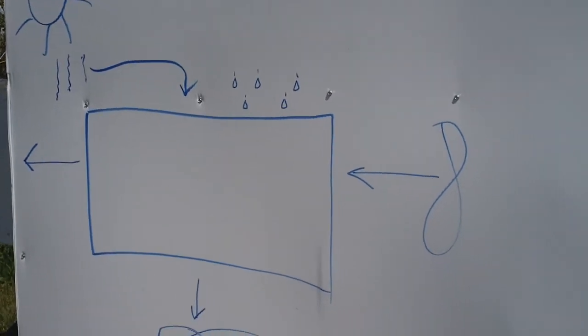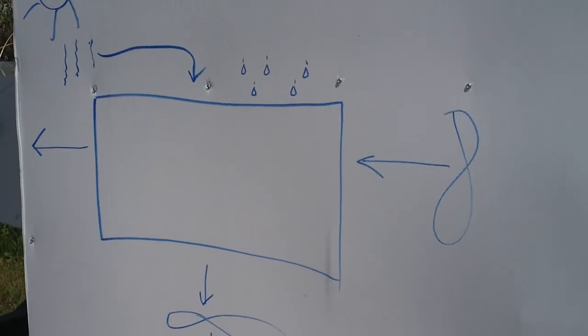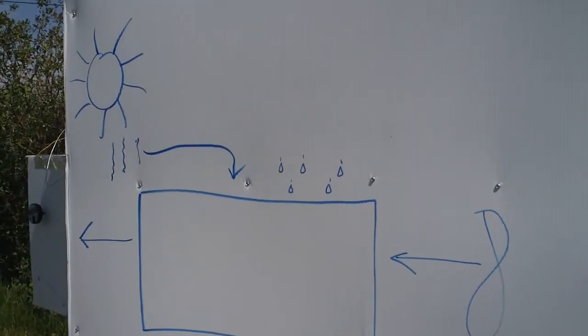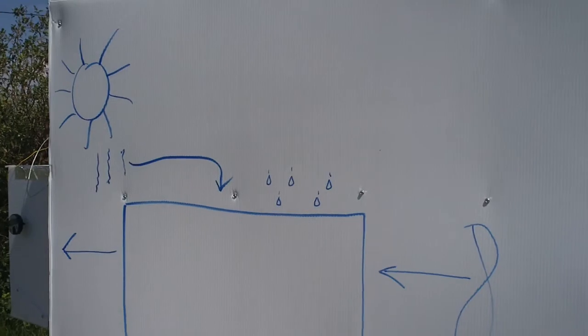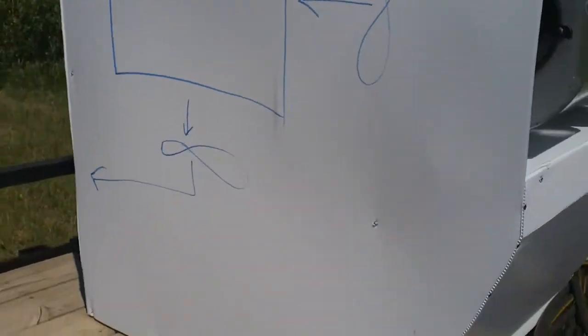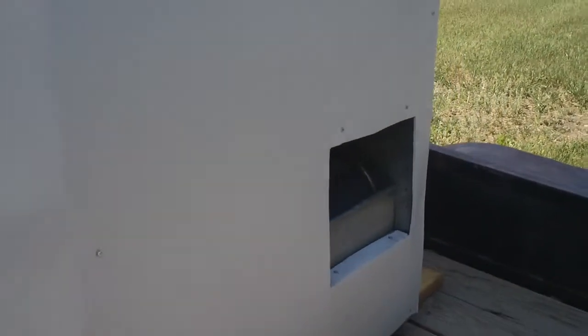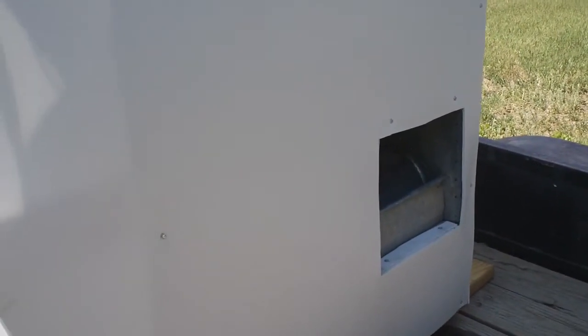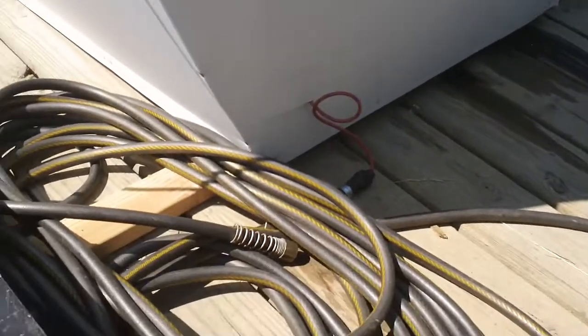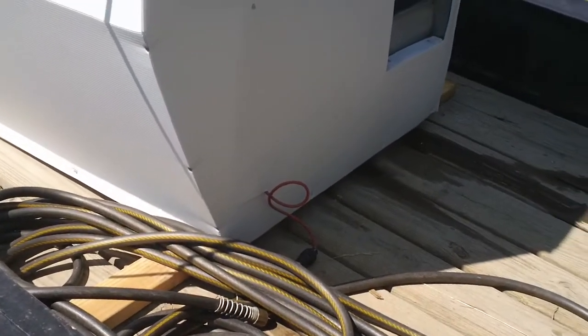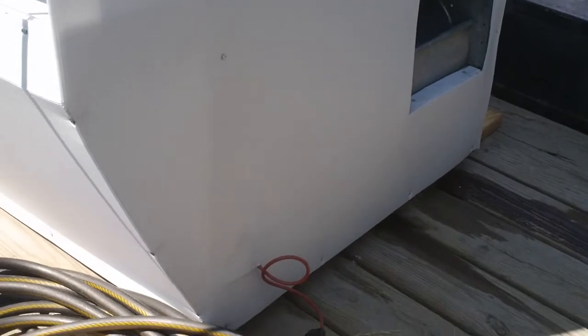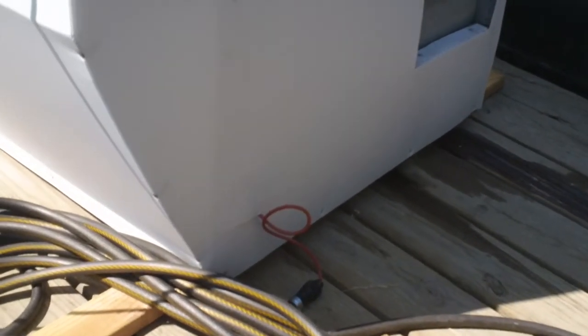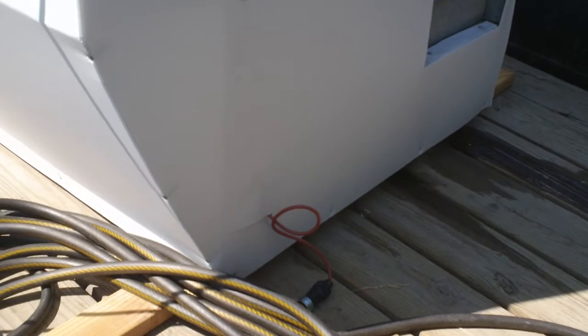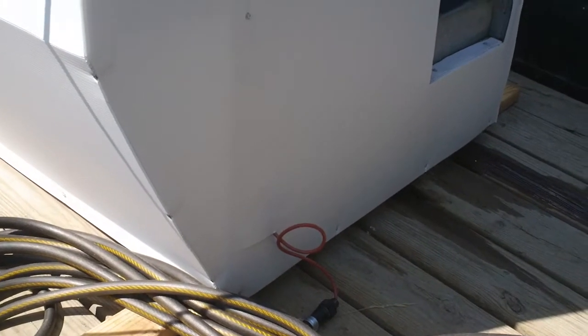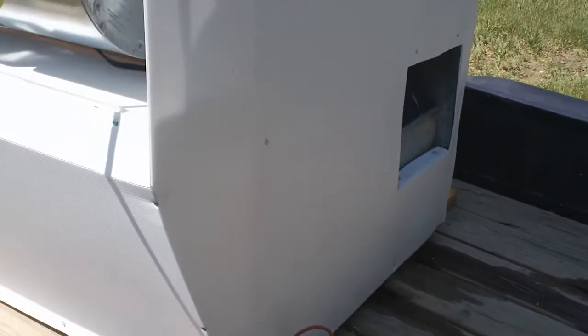This is an indirect evaporative process. Water's being dosed into the top, as well as we're pulling ambient air through using about a 4-ton or 1400 CFM squirrel cage blower, which is jettisoning out the side here. So that's pulling water out. Right now we have all this garden hose, but we're not hooked up. The sump has water in there, and much like a swamper, we use a float valve to control the water level inside. So that's where we're at right now.